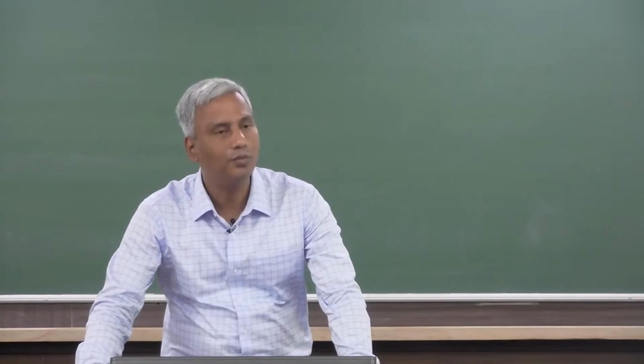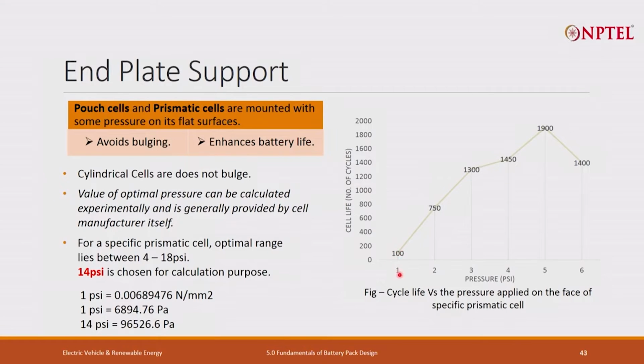1900 versus 100 - basically, if you're not providing pressure, you're allowing the cell to swell freely. Here, you are providing an optimum pressure that comes between 4 to 18 psi to get the maximum benefit. However, it's impossible to always maintain the same pressure - it will vary depending upon the cell expansion and contraction. So somewhere in this range, 3 to 6 psi, you get from 1300 to 1900 cycles, not 100.